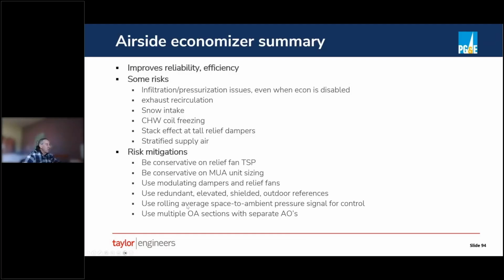And so what we use is, especially with doors open, things like that, you can actually have a fairly noisy signal. So what we do is use a rolling average. It might be like a 2-minute rolling average. So it's sampling space pressure every, say, 10 seconds, and then averaging those signals over a 2-minute period to tell you, okay, here's a smoothed out, less noisy signal of what you really are controlling, what your real pressure is. And that's a better way to modulate your relief and make sure your space is positively pressurized.